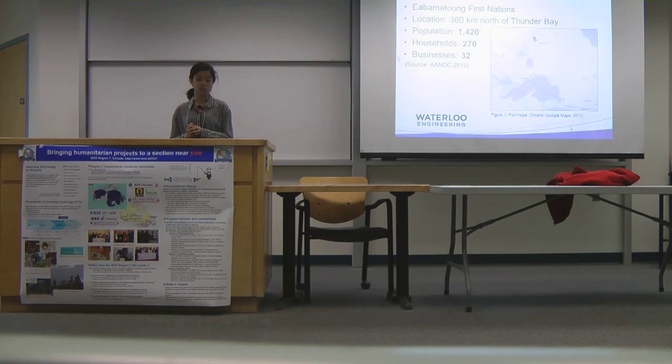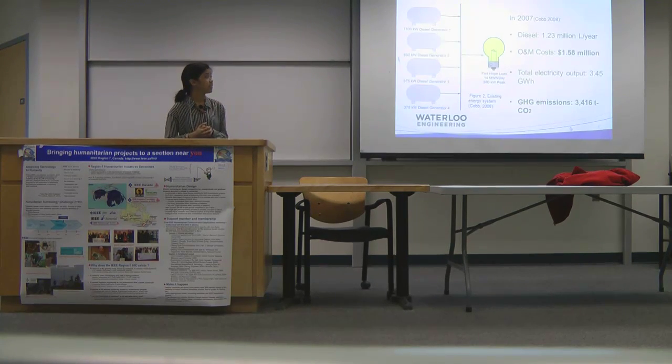So the selected community of Fort Hope is located 360 kilometers north of Thunder Bay, and they have a population of around 1,400 people. The existing energy system at Fort Hope consists of 4 diesel generators of different ratings, and they have a peak of approximately 990 kilowatts. Their diesel fuel consumption, based on a study done in 2007, also resulted in an O&M cost of $1.58 million per year. And their greenhouse gas emissions were also around 3,400 tons for the year.